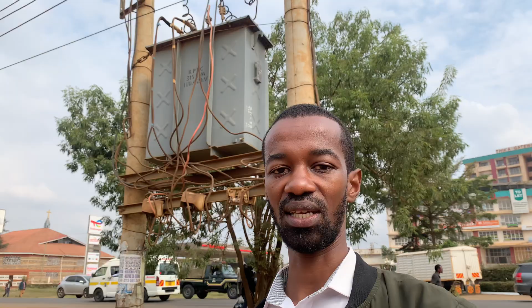There's something I'd want to talk about, and this is the neutral. The neutral is the return path for all the phases in this transformer. It serves the red phase, the yellow phase, as well as the blue phase. Every load connected to a particular phase is returned by the neutral to the source, which is the transformer. I need to emphasize that in case the neutral breaks, there needs to be something referred to as a floating neutral.